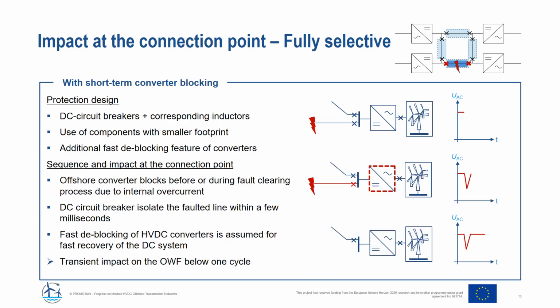So during the fault clearing, the offshore converter blocks, but still the DC circuit breakers isolate the faulted line within a few milliseconds. To then be able to achieve a fast deblocking, all the system parameters have to be back in their operational ranges. So, for example, the DC system voltage has to still be in the operating band of the DC converter after fault clearing, and also the internal current thresholds and submodule voltages have to be in an allowable band. In that case, the fast deblocking can take place. And this is typically achieved below 1 cycle, so then there's a transient effect on the offshore system, for example here shown in the AC voltage, below 1 cycle.